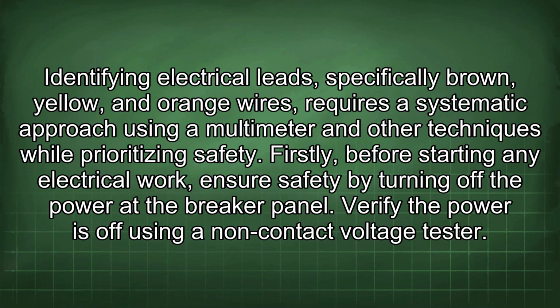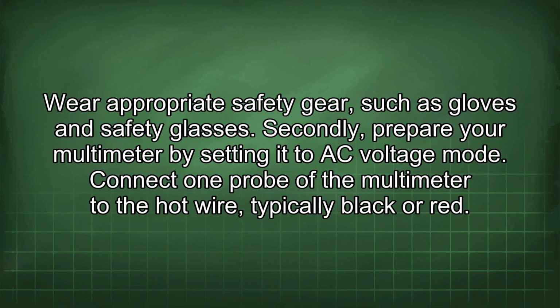Identifying electrical leads, specifically brown, yellow, and orange wires, requires a systematic approach using a multimeter and other techniques while prioritizing safety. Firstly, before starting any electrical work, ensure safety by turning off the power at the breaker panel. Verify the power is off using a non-contact voltage tester. Wear appropriate safety gear such as gloves and safety glasses.